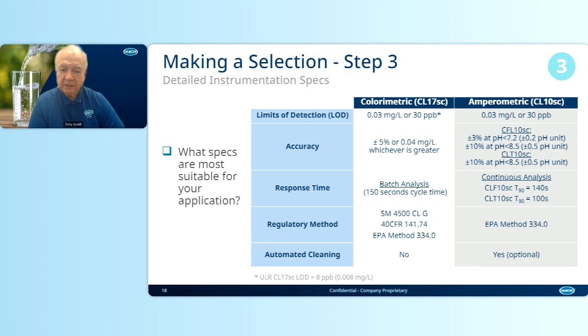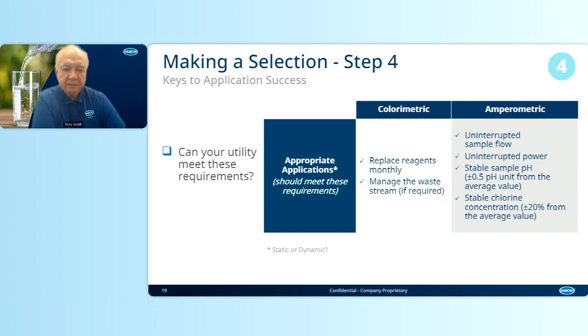Automatic cleaning is not available on the colorimetric. It is available on the amperometric for an optional cost. Okay. Can your utility meet the requirements? Can I replace the reagents monthly on the colorimetric and manage the waste stream if required? On amperometric, I need to be able to have an uninterrupted sample flow, uninterrupted power, stable sample pH, stable chlorine. All those need to be that way because the amperometric probe requires it.